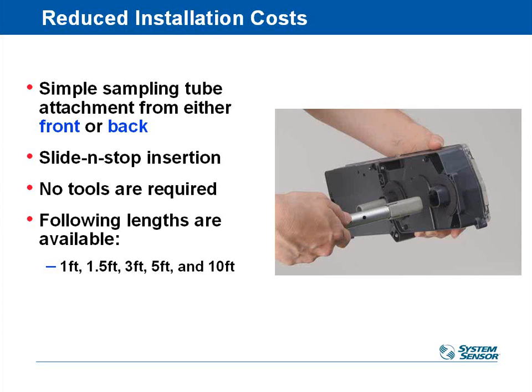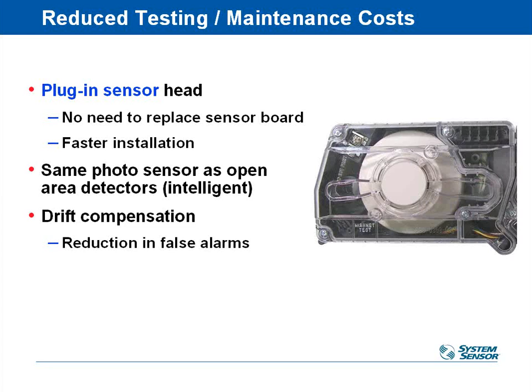So the reason I mention that is people sometimes confuse that little 3-inch discharge tube with a sampling tube and think that's all they need. You do not. You always have to order a sampling tube, always, for every manufacturer.